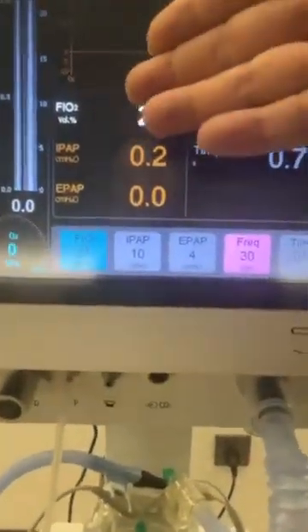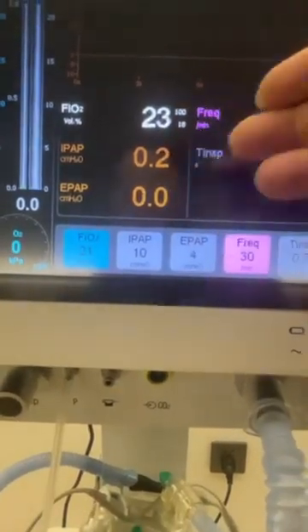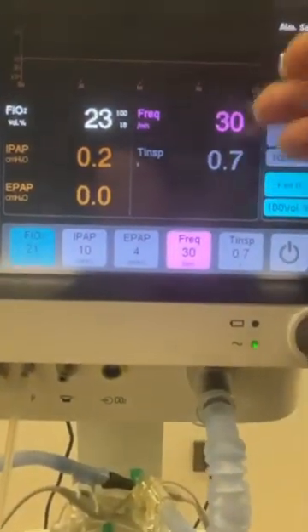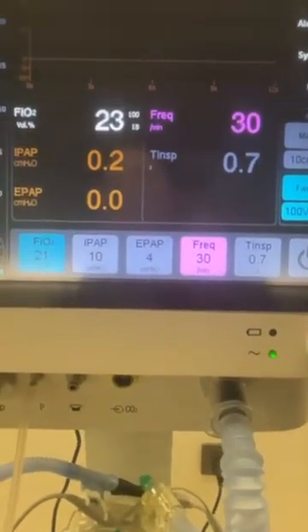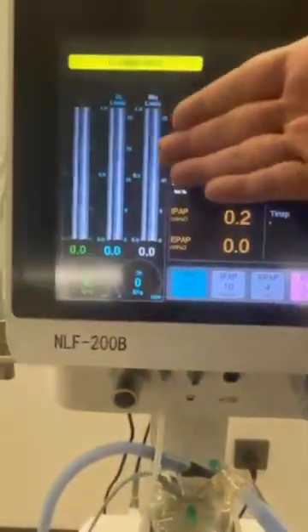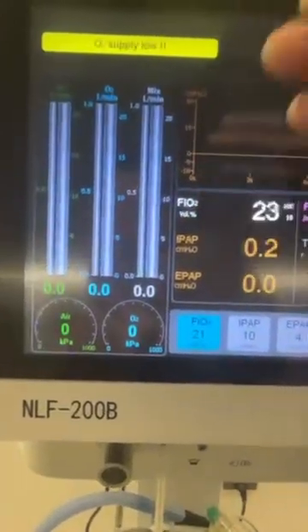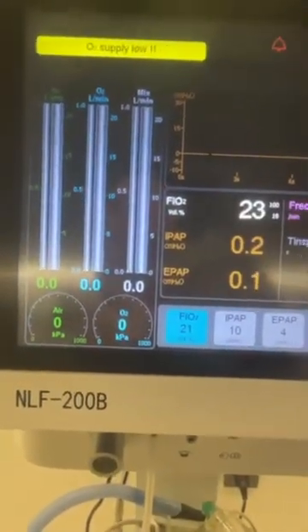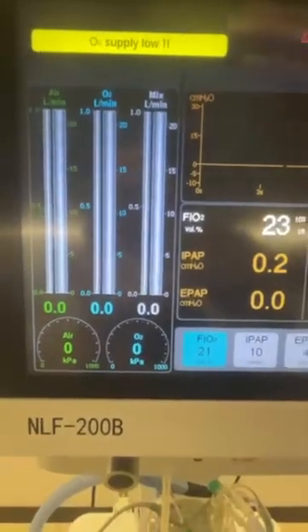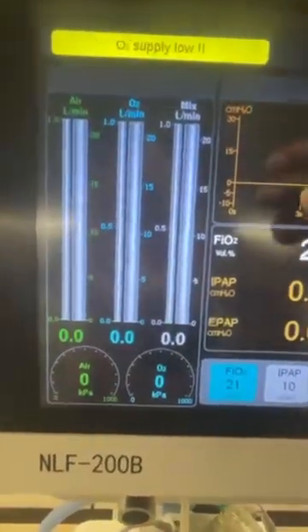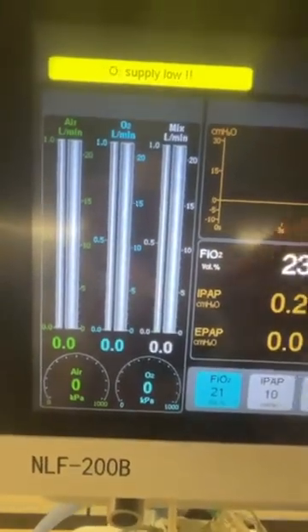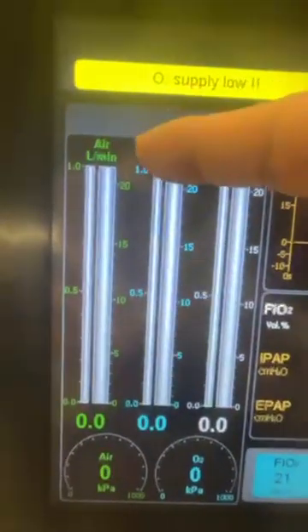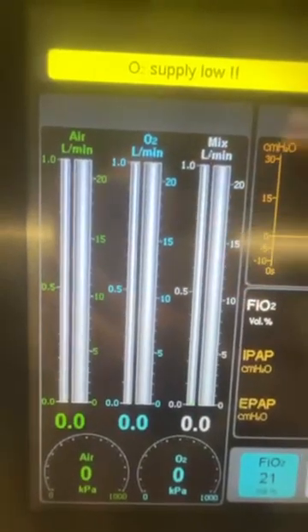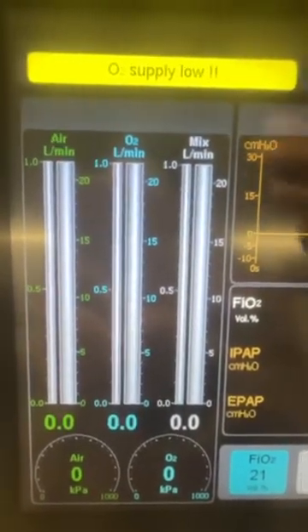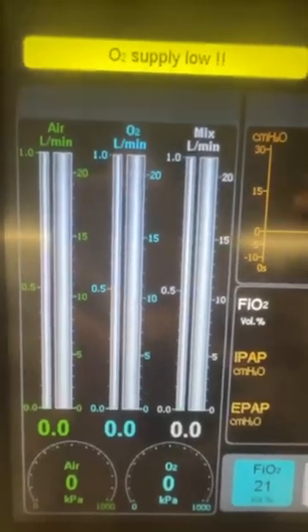And here, at the same time, we can also show some parameters like the oxygen concentration, the IPAP, EPAP, breathing frequency, and inspiration time. So it can help the doctors much more to know the situation of the patient. Then, by the left side here, we can show the flow meters. For this machine, we are using the electric air and oxygen blender. So all of the flow status will be shown on the screen directly and much more clearly. As you can see here, the first column is for the air, the second column is for the oxygen, and the last one shows the mixed gas flow. So it will be easy for you to operate.